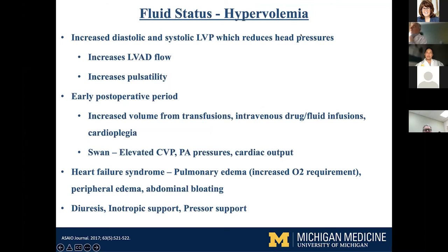In hypervolemia, increased diastolic or systolic LV pressures can reduce head pressure and increase LVAD flow. If somebody is fluid overloaded, you get a large increase in LVAD flow for a given speed, and it can also increase pulsatility as the heart ejects blood from the aortic valve. This often happens in the post-op period — someone who's gotten a lot of transfusions, IV drugs, or fluid infusions. You would correlate increasing flow with elevated CVP, PA pressures, and cardiac output on the Swan.